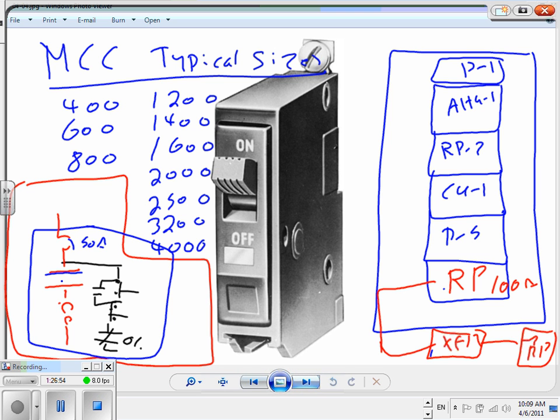Well, there's a couple of panels that you have to feed out of it, feed 120. Oh, there's a bus duct. Yeah, 208/120 bus ducts. The same thing. How are you going to match a receptacle panel transformer to the bus duct? Just to give you a hint, guys, we size the transformer based on the load. Go to KVA, find what your KVA is, and then go to the next standard KVA and try to match, Camille, my friend, the panel to the full load current of the transformer on the secondary side.